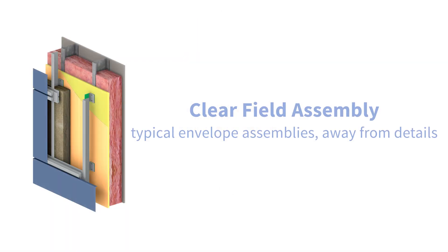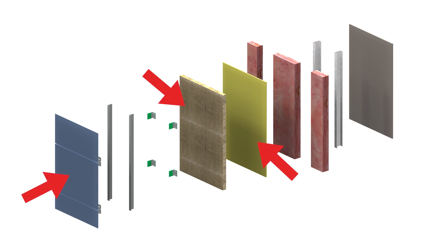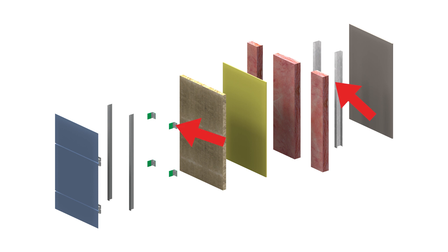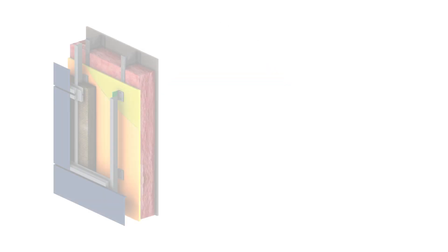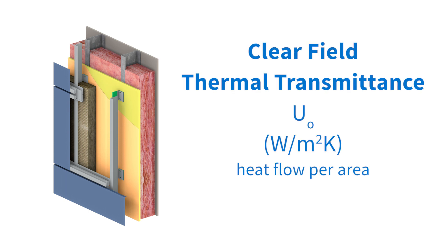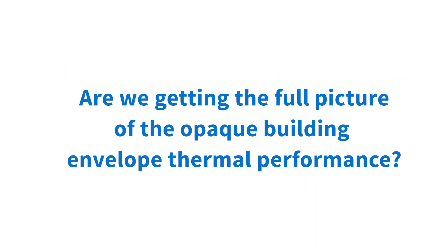The clear field. The first thing to include in a U value calculation are clear field assemblies, which are the main types of envelope constructions on a building. Clear field assemblies typically include sheathings, cladding, insulation, and other components, but also include frequently repeating thermal bridges that would be too cumbersome to count up individually. This includes thermal bridging components such as studs, brick ties, and supporting cladding or girts, but not transition details such as slab edges, which are accounted for separately. For each of these assemblies there is a clear field U value — the heat flow per area — that includes the impacts of these uniformly repeating thermal bridges. If only clear field assemblies are being looked at, which is current standard practice in North America, are we really getting the full picture of the heat flow through the opaque building envelope?